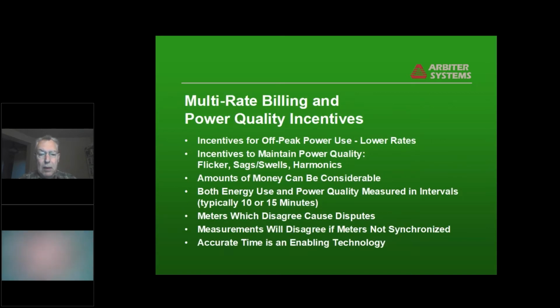Multi-rate billing, power quality incentives. There's incentives to companies to use off-peak power, and they get lower rates for that. So when you do that, the billing, the energy meters have to be synchronized in order to know what time it is. And very often that's done with a clock in the substation or near the customer's site where the meter is, that's synchronized with IRIG or SNTP or something like that.